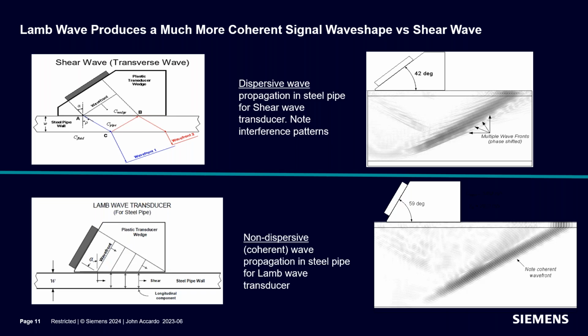If we look at a Lamb wave, the beam comes into the pipe at a predicted angle where we know it's going to refract to the 90 and travel down the pipe wall. And that's going to cause the pipe to vibrate at the normal, vibrate up and down, and transfer that energy into the flow stream. That wave is going to be very coherent. It's non-dispersive. And so it stays constant as it travels down the wall. If you look at the right side of the screen, you see the wave fronts are nice and evenly spaced, very coherent. And in the pipe wall, you can see how they're perfectly vertical and evenly spaced. There's no disruptive wave pattern in the pipe wall.